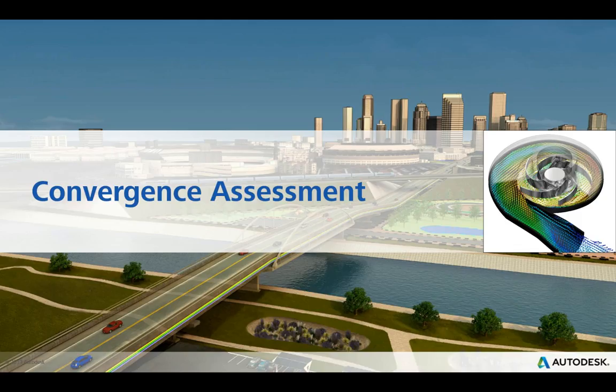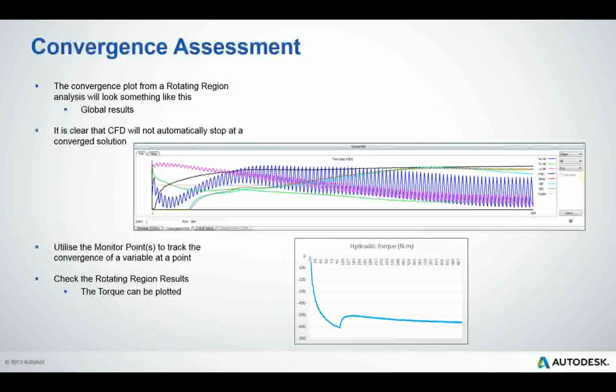Once the model is running, assess convergence to ensure we're moving toward a converged solution. For most analyses CFD automatically stops when converged, but with rotating machinery we're plotting all variables globally over time and most velocity components are cycloidal. Instead, look at the pressure curve — the black line — which is fairly smooth, or use monitor points tracking pressure or flow rate at the outlet. You can also stop the analysis and look at rotating region results to plot torque over time, showing an initial large impulse as the impeller starts moving, then gradually stabilizing.